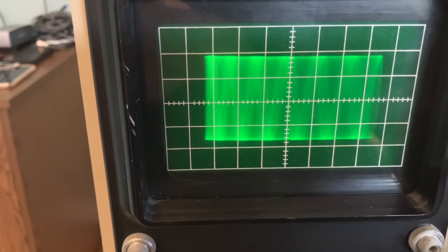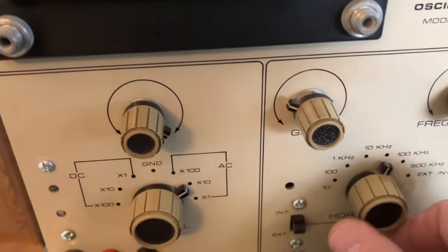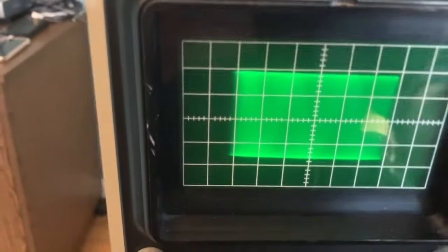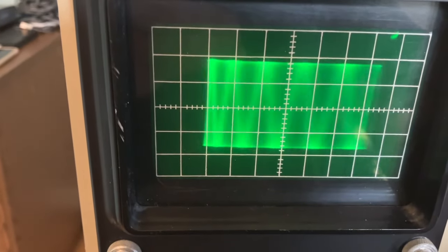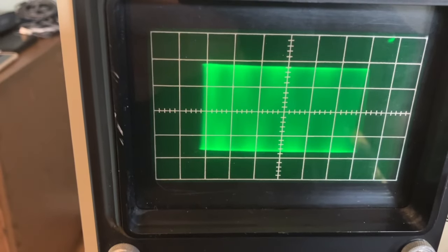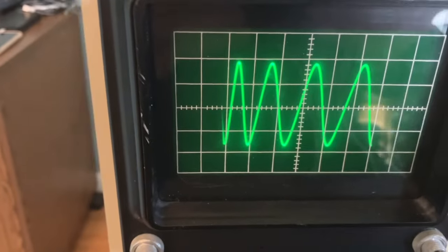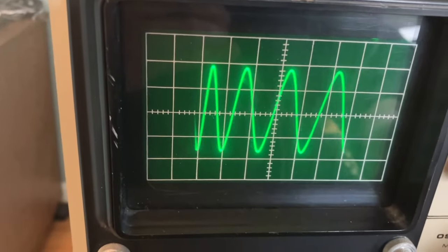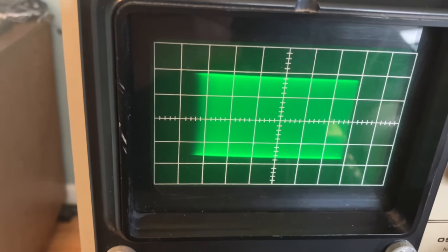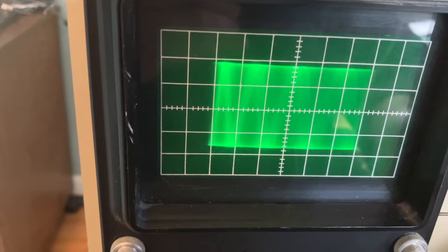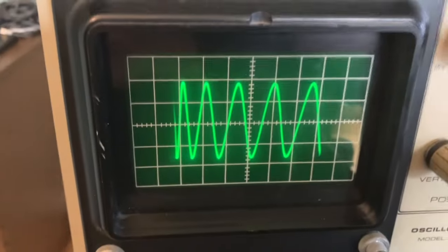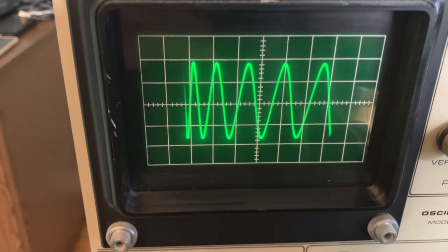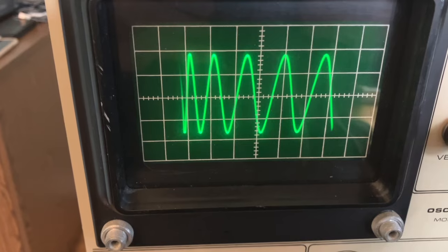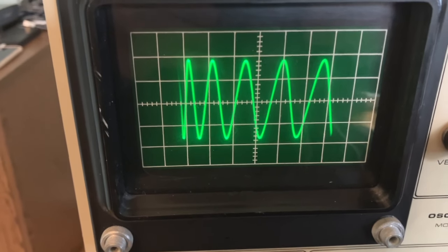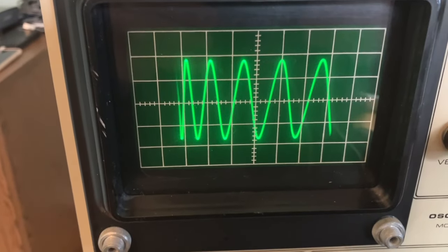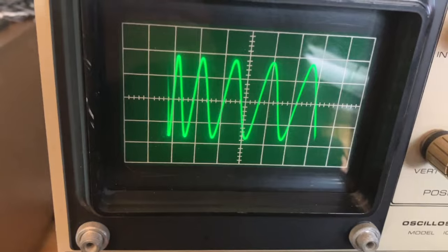And this is how it's rated. Actually, we can go to the final sweep frequency and try and get a waveform out of that. There we go. So there's 1, 2, 3, 4 cycles of 5 megahertz. Is that going to be it? Yeah, that's at the top end. So this is the top end of its sweep range, and obviously the amplitude is down, but still within spec. But the linearity left a bit to be desired. So will it display 5 megahertz? Absolutely. We could even try and go a little bit further.